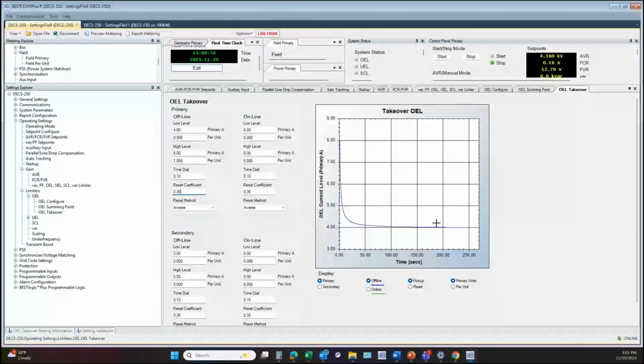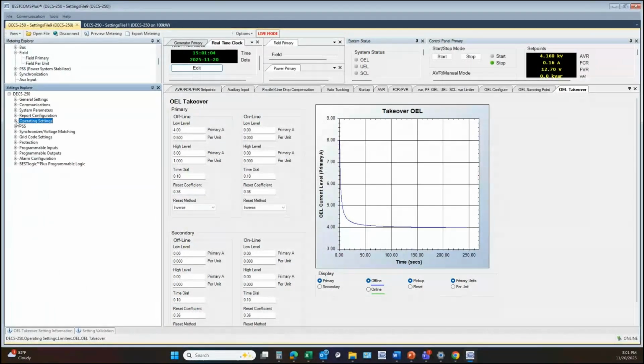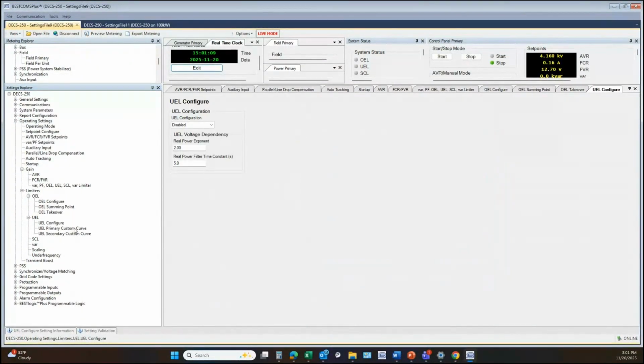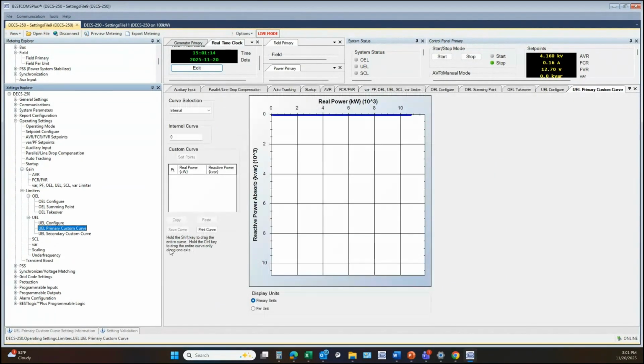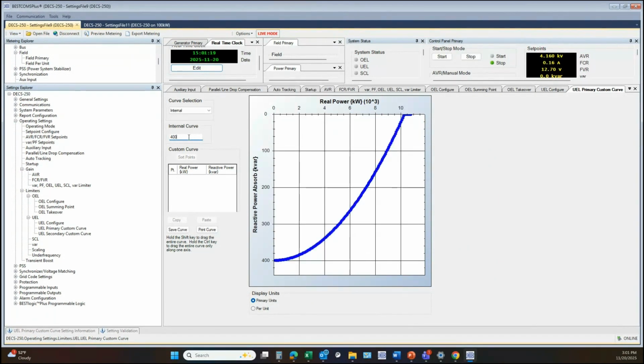So your limiters need to be coordinated with whatever other protection you have in place. The UEL is the under excitation limiter. I mentioned that in that generator capability curve, you're trying to stay above that under excited limit. So you would define a point where you're producing zero real power, how many kvars your machine can absorb, and then it will create a curve from there. Or you can set up a custom curve where you're defining several different points to create your own curve. But your machine's rated data should have that information as well. Again, it should have a capability curve. You should be able to set that under excited curve based upon that capability curve of the machine.